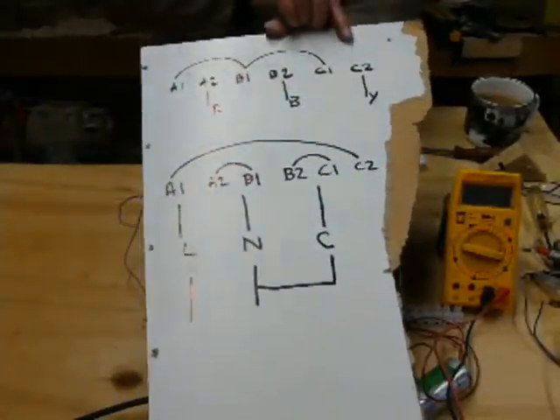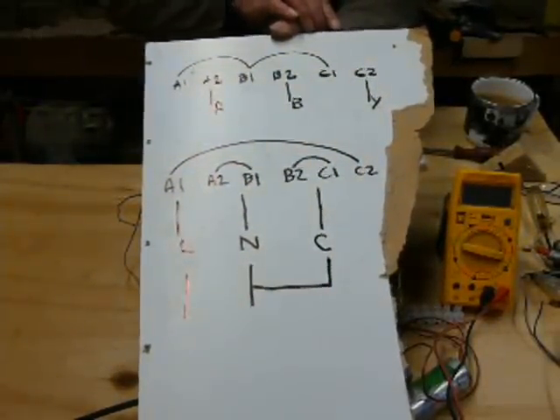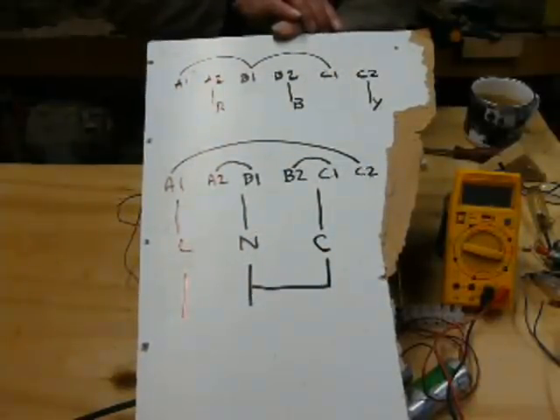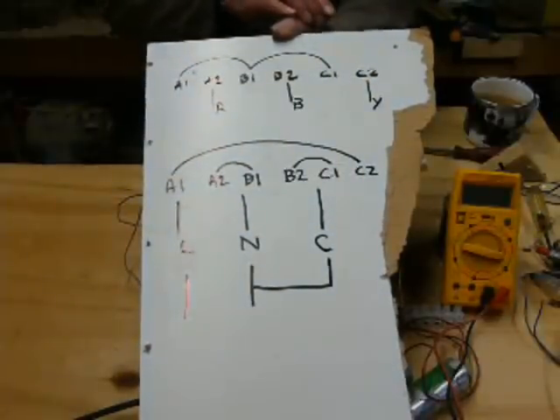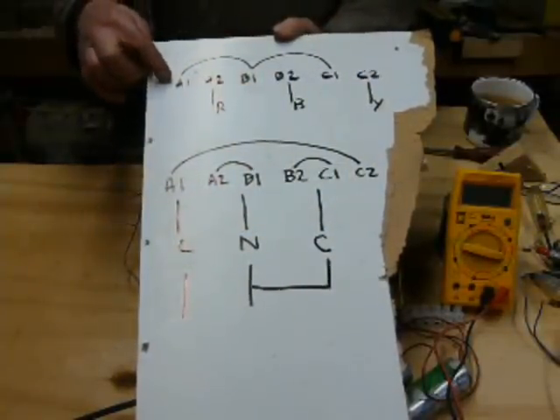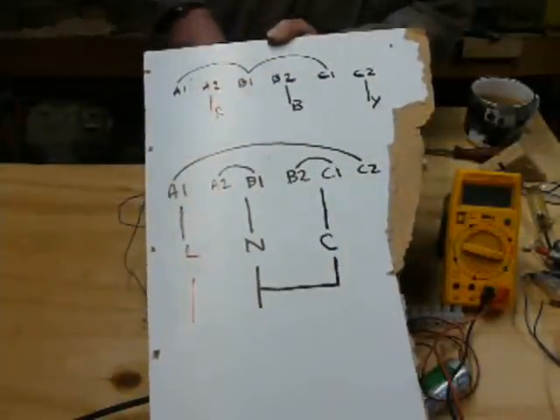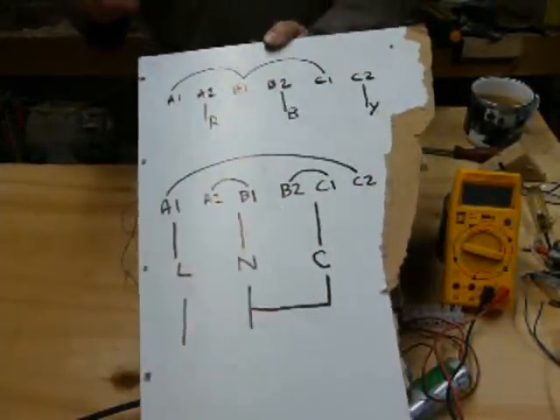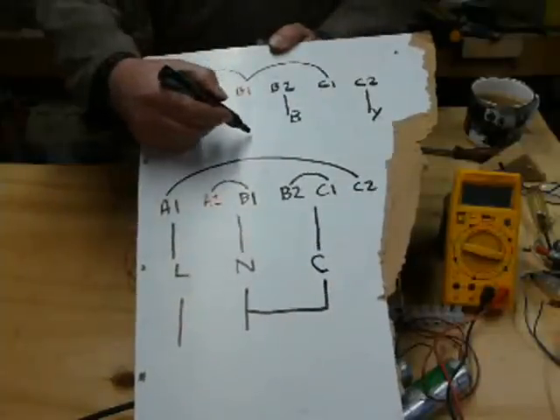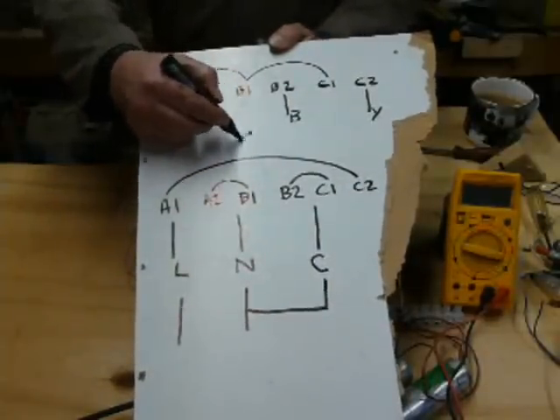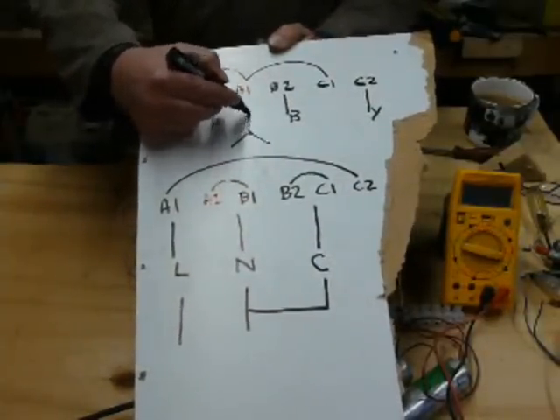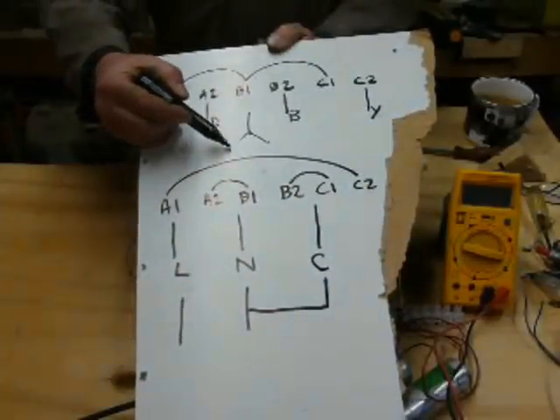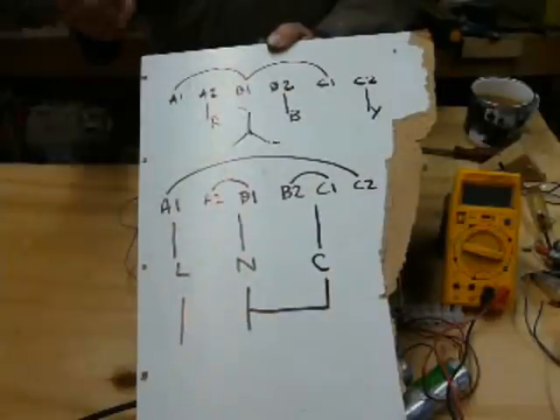This is how it was wired when I took it off. The motor plate said 440 or 240, but it was wired for 440. So what we've got is A2, B1, and C1 all connected together. Where's my pen gone? Here it is. So if A2, B1, and C1 are connected together, then we've got star, with the red, the blue, and the yellow going into there, there, and there.